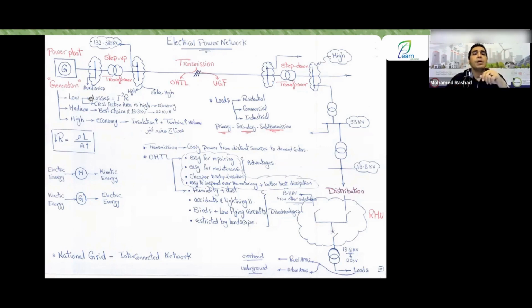So someone might say, why worry? Just generate high voltage. And you say, okay. They tell you, high voltage means low current, and you agree. They say, this means the cross-sectional area of the conductor becomes smaller. You no longer need a large cross-sectional area to carry the currents, and therefore the cross-sectional area of the cables or the trenches will also be small. All right, guys, so the cable's cross-sectional area has become smaller, which means your cost has decreased.